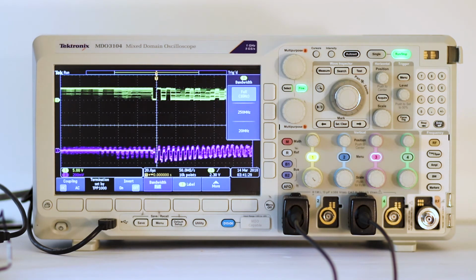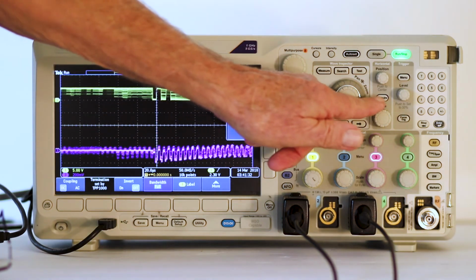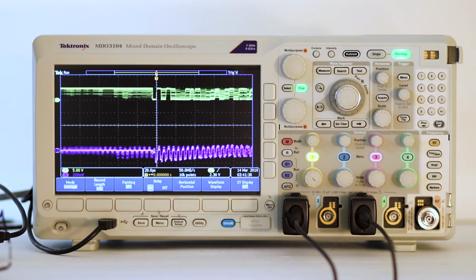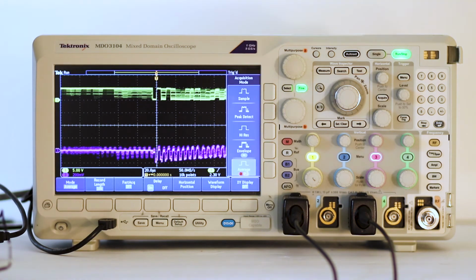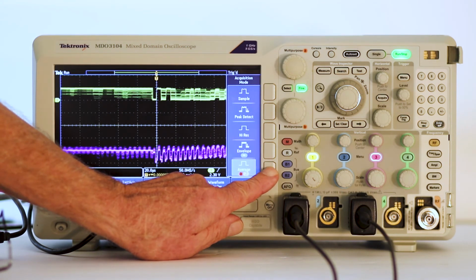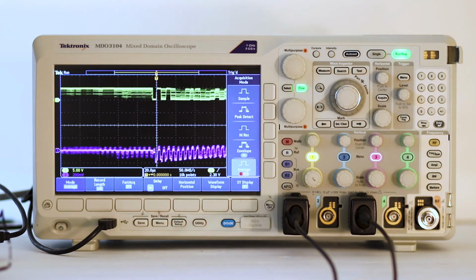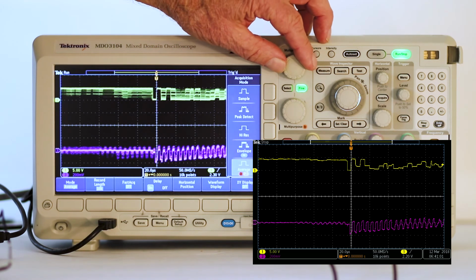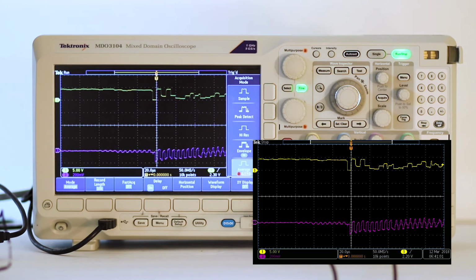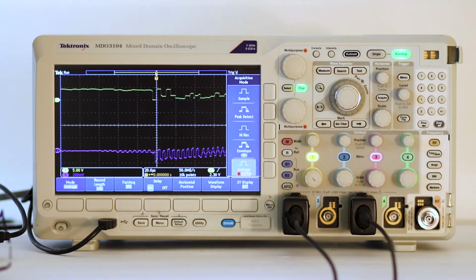To perform signal averaging, press Acquire. Then press the soft key associated with Mode in the bottom horizontal menu. This brings up the vertical acquisition mode menu on the right. Press the Average soft key. The number of waveforms that are averaged can be set by turning multipurpose knob A or by using the number pad. The range is 2 to 512. As you can see, the distortion is removed, leaving a good display.